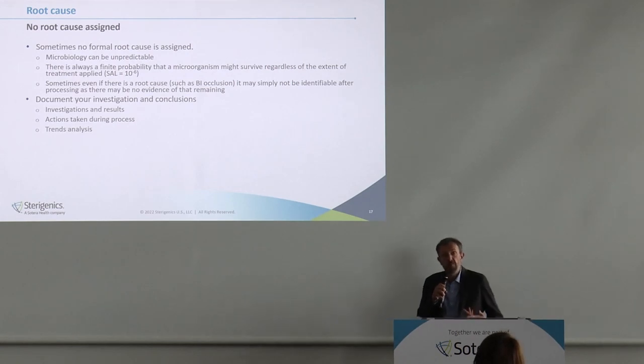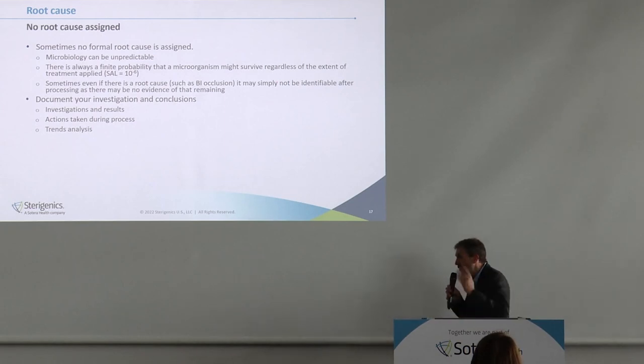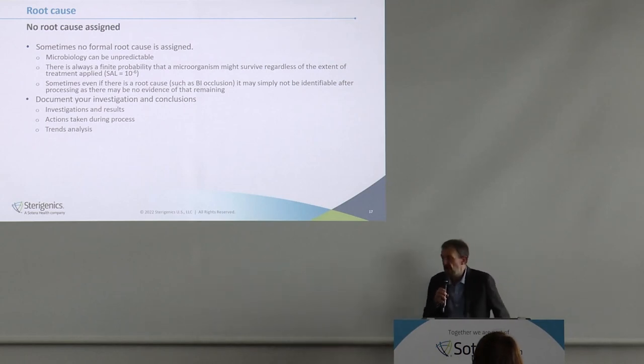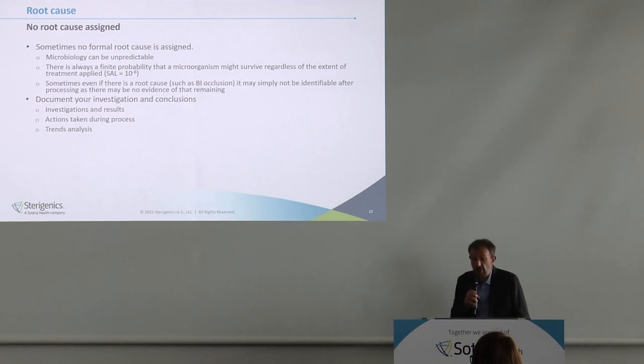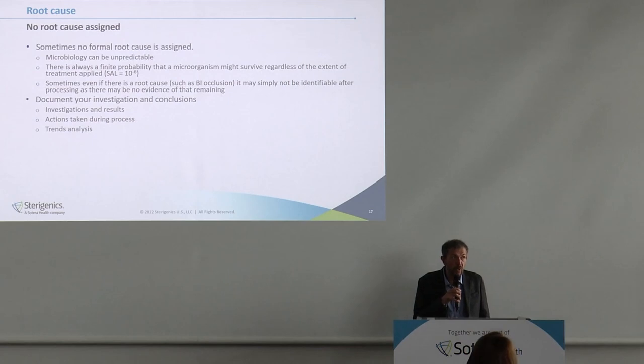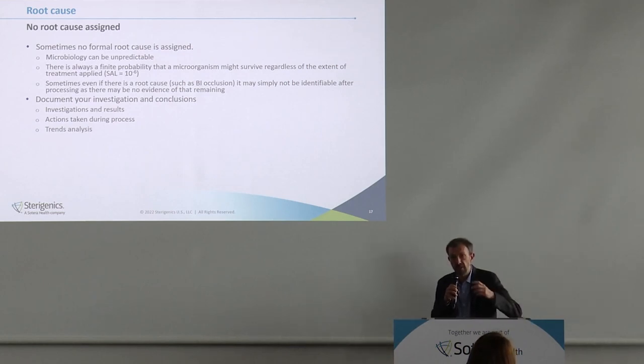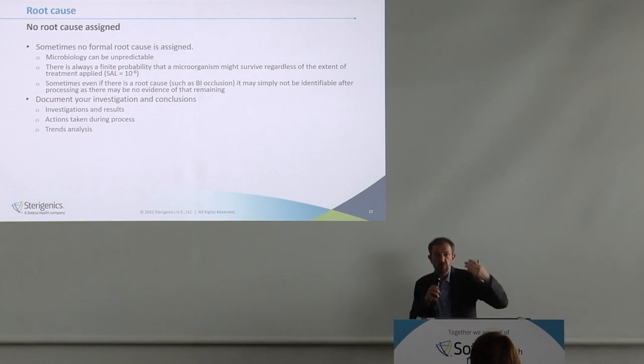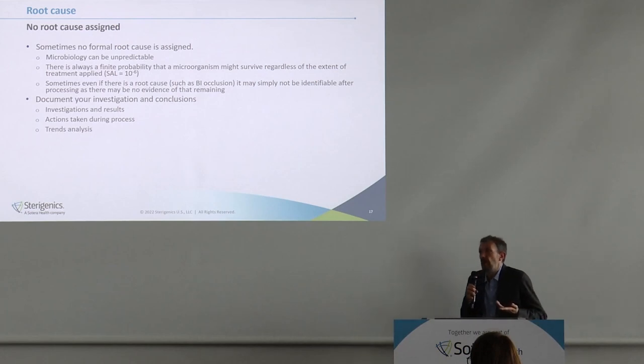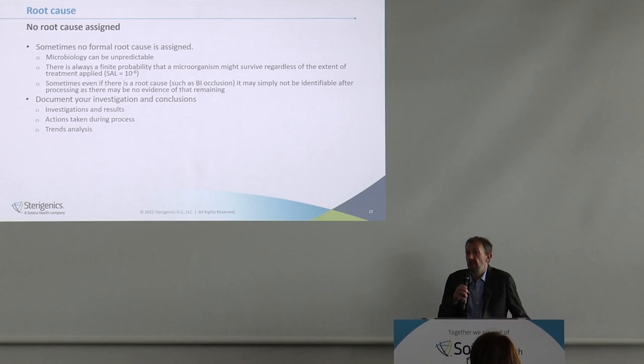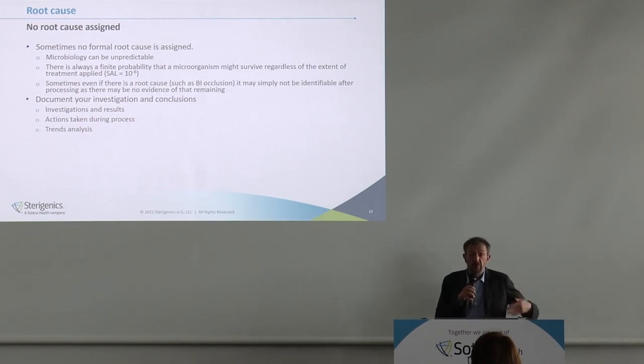Unfortunately, most of the time we may not find any root cause. We're talking about living organisms — they might behave differently, like human beings. We could have situations where we think something happened but cannot prove it. For example, BIs placed in PCD tubing might experience kinking that blocks gas access when vacuum is pulled — we believe it but can't prove it because we can't take pictures during the cycle. If we cannot assign a root cause, we still need to document it, perform trend analysis, and assess the impact.